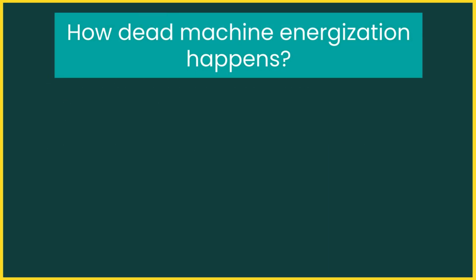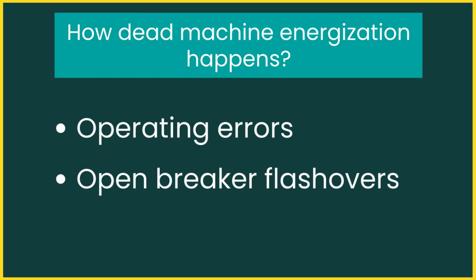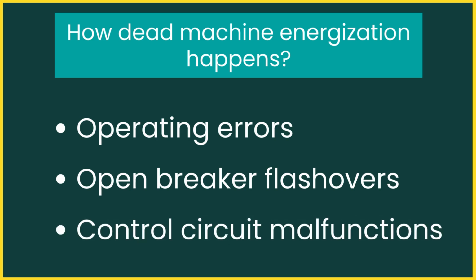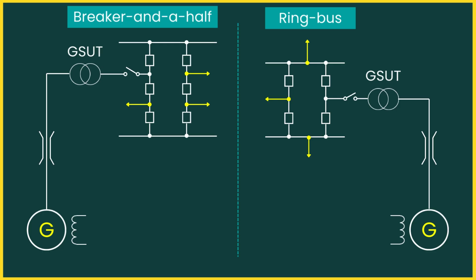Let's start with how it happens. There are three main causes: operating errors, open breaker flashovers, and control circuit malfunctions. Sometimes, they even occur together. Operating errors are more common today because of breaker-and-a-half and ring bus configurations. These setups improve flexibility and reliability, but they also make switching more complex. With more breakers and more paths involved, a single operator mistake, or a control issue, can easily connect the grid back to the generator, causing inadvertent energization.